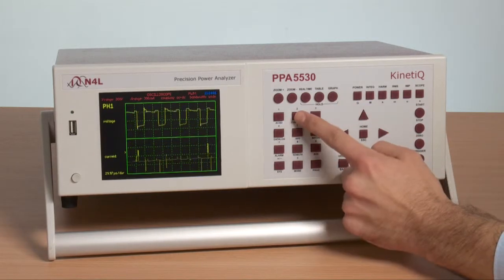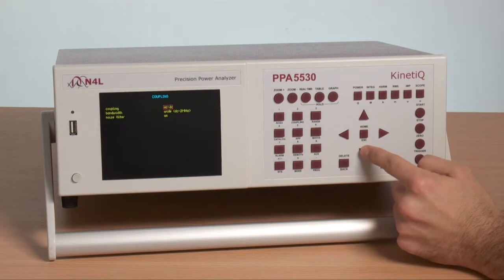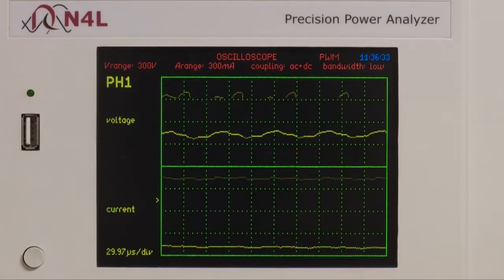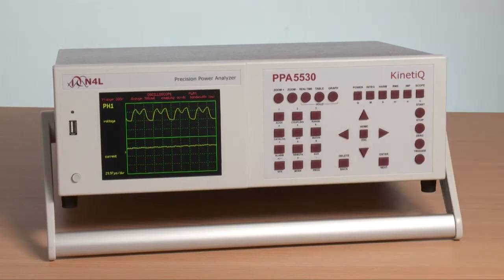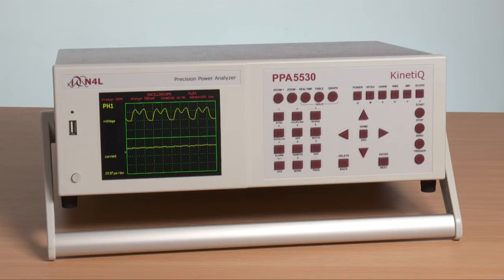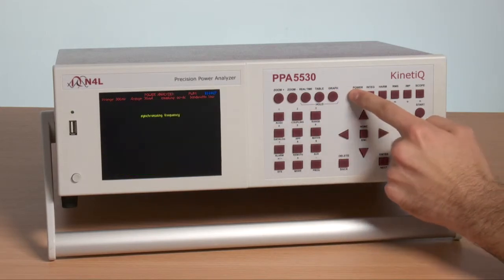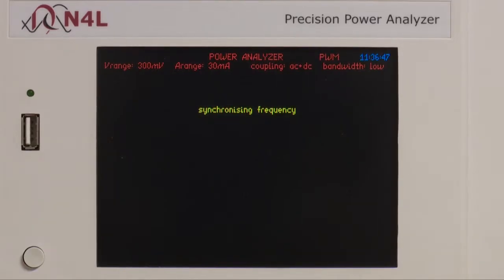We can now change the bandwidth back to 30 kHz and pause the display again. It can easily be seen that the waveform rise time has been significantly reduced by filtering. This will inevitably influence the accuracy of total power measurement. We can illustrate this in more detail by looking at the voltage in the power screen while we are still in low bandwidth.